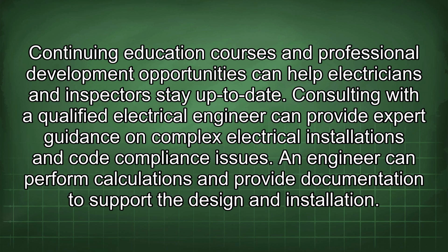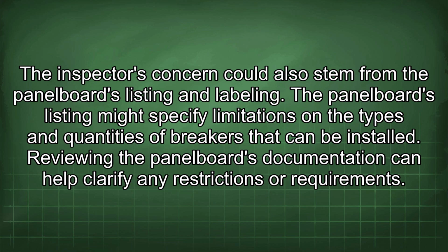Consulting with a qualified electrical engineer can provide expert guidance on complex electrical installations and code compliance issues. An engineer can perform calculations and provide documentation to support the design and installation. The inspector's concern could also stem from the panel board's listing and labeling. The panel board's listing might specify limitations on the types and quantities of breakers that can be installed. Reviewing the panel board's documentation can help clarify any restrictions or requirements.